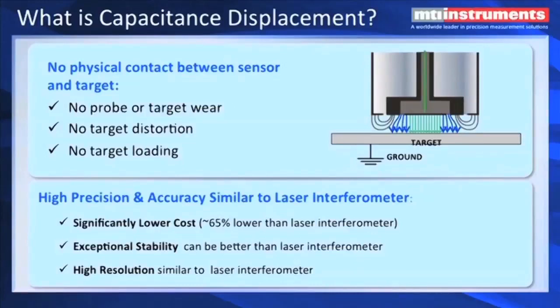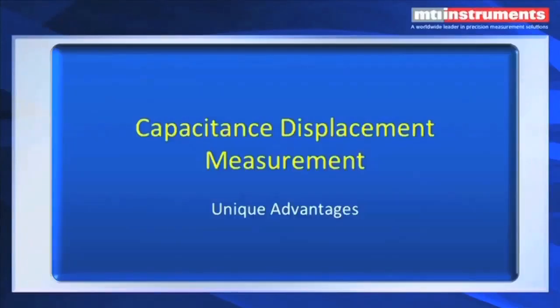The other interesting thing about capacitive displacements is the very high resolution and accuracy we get. It's very similar to laser interferometer, but at a much lower cost. And it can actually have higher stability than some lasers out there. And the resolution is about as good as a laser interferometer, in some cases higher. What are some of the unique advantages of capacitance displacement measurements?